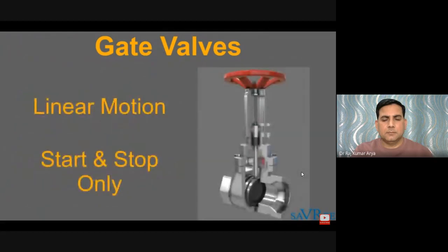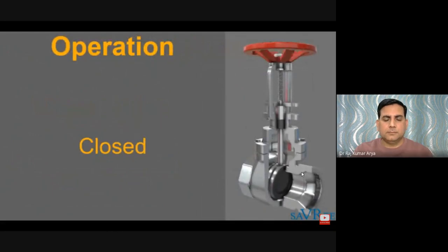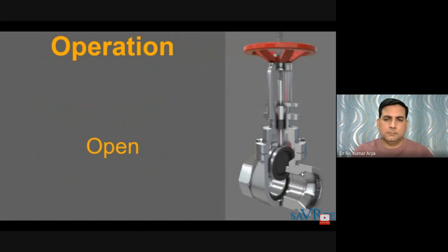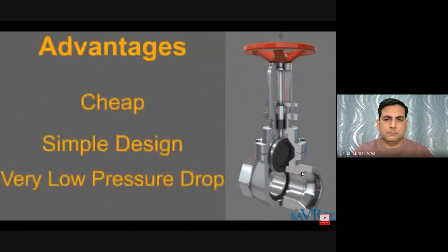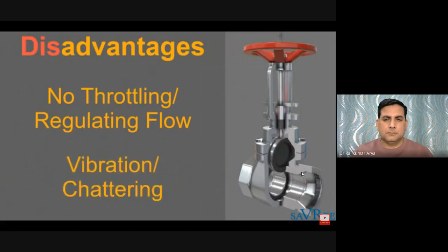Gate valves are the most common type of valve used today. They are linear motion valves used to start or stop flow, but are not suitable for regulating flow. The disc is completely removed from the flow stream when fully open, allowing flow with virtually no resistance and a very low pressure drop. The main advantages are low cost and very low pressure drop when fully open. Disadvantages include unsuitability for throttling, excessive vibration when partially open, and greater susceptibility to seat and disc wear compared to a globe valve.